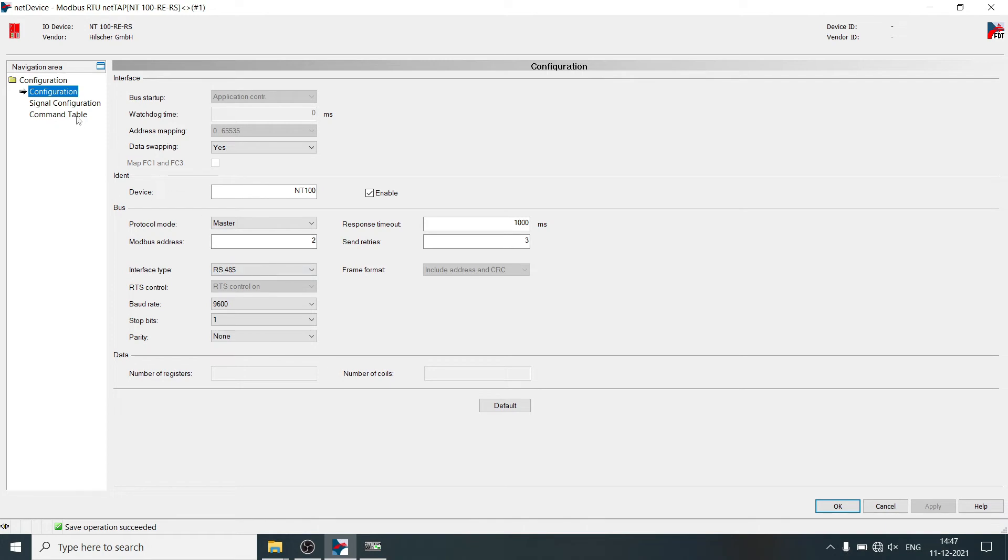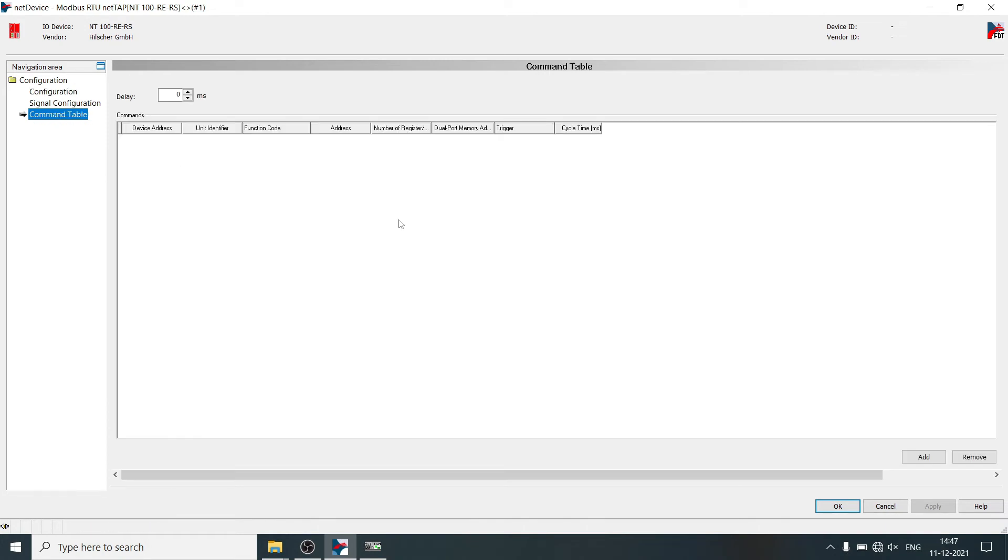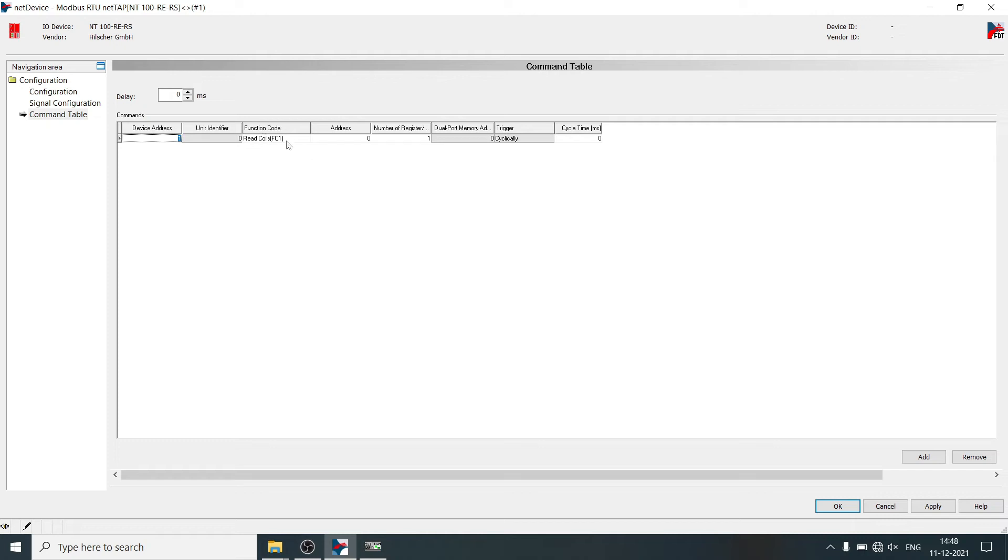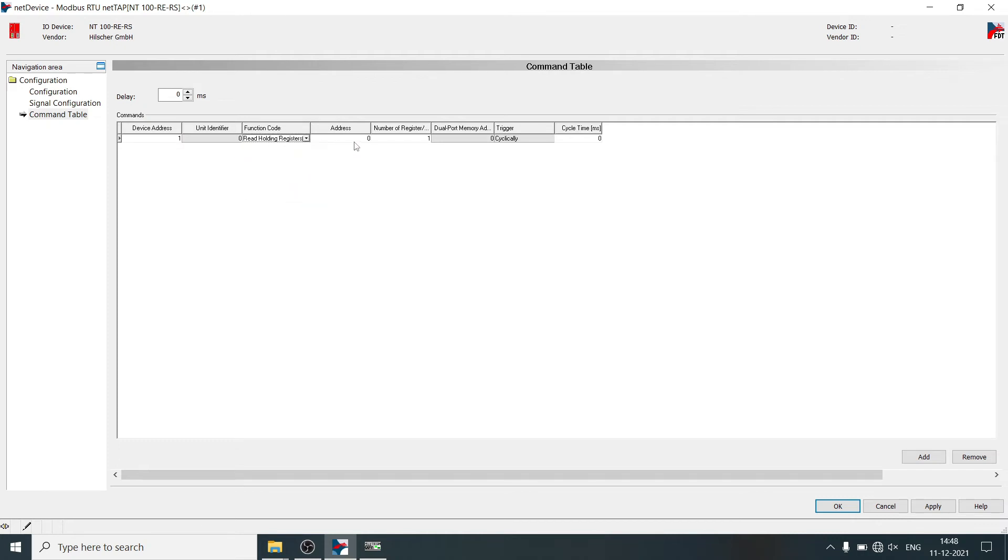Select command table. Click on add. Define node address of energy meter. Select function code as read holding register. Define parameter address.